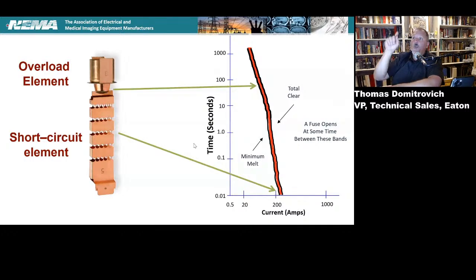Now, what that does is helps you shape the curve in the overload region. What we will also do to further shape that curve, maybe down there where it says minimum melt, where that arrow is pointing in that region, they'll put what they call M spots, I think they call it, where they'll put a little dab of a material on the element, on that short circuit portion of the element, which will help it shape, again, that curve.